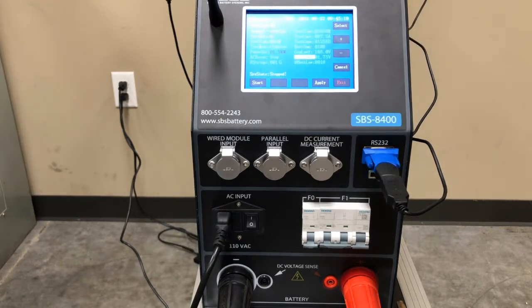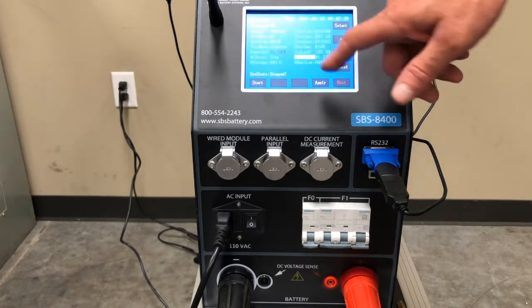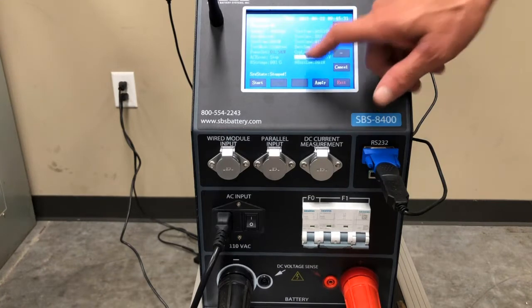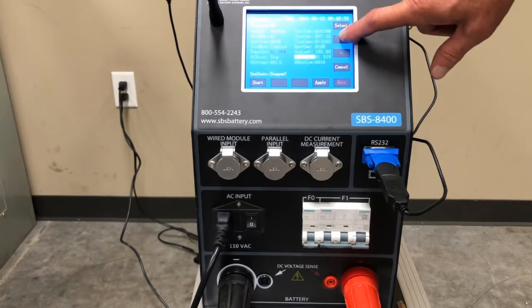Battery low voltage. If I'm using the wireless modules, battery low voltage is the voltage that I want that module or battery to alarm at, not to stop the test at. So in this instance, 12-volt block batteries, 1.75 volts per cell, my battery low voltage is going to be 10.5.